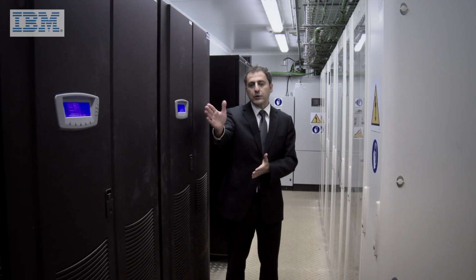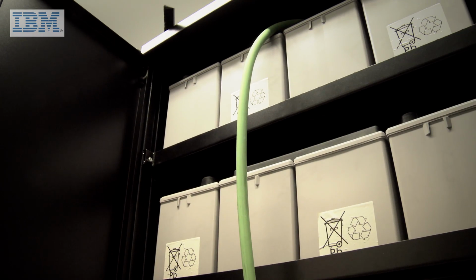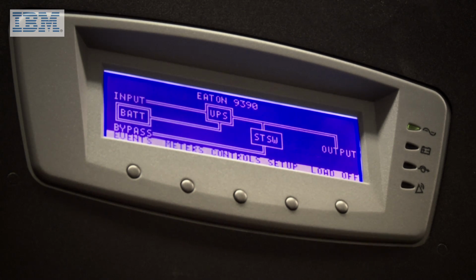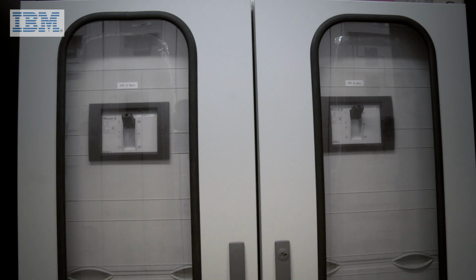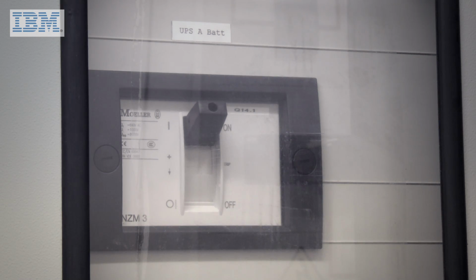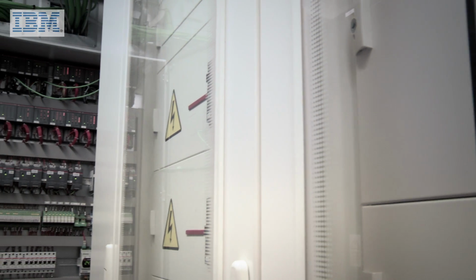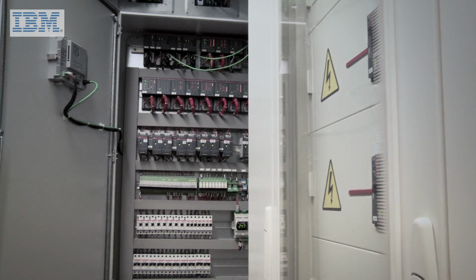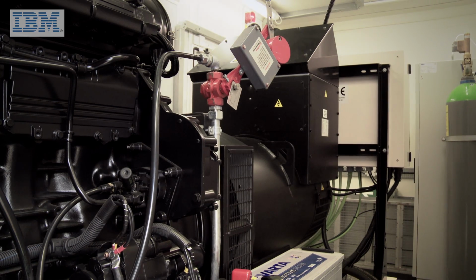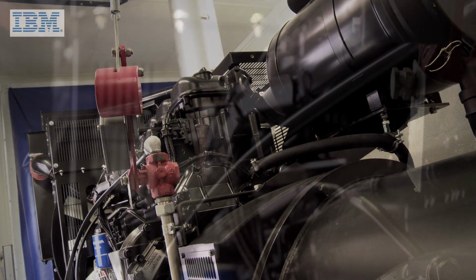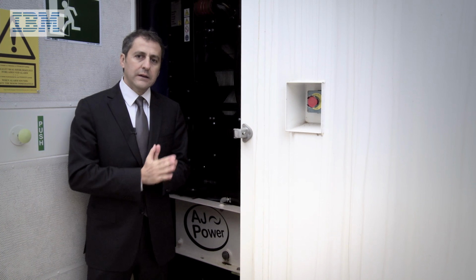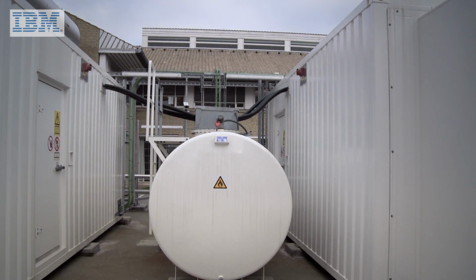This is the power container, where we have a UPS-A and a UPS-B with dedicated batteries with 20-minute backup time, each of them providing power to the IT modules that we saw before. We have also switchboard A and switchboard B, providing power to the entire facility, including natural free cooling systems and chillers. Also at the back end, we have the SCADA system managing over 400 signals, which control the entire facility. This is one of the two redundant motor generators that provide backup power to the entire data center facility. Each of them is 650 kVA and has a 72-hour fuel tank with double pump.